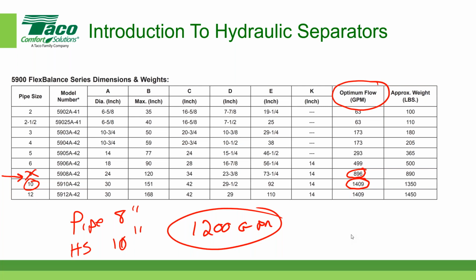But most engineers will have information in their specification that says the system has to be flushed and strainers have to be cleaned before the system is turned over to the owner or the long-term operator. The point they're trying to make is that the water or the solution, in this case water or water glycol, the most common, needs to be as clean as possible. Once you get the initial circulating and you clean out the system, you add the chemicals and all of those other maintenance related things, then what I recommend is that you blow down your air and dirt separator. You open the valve at the bottom of the air and dirt separator once a day for a few minutes to check how clean the water coming out is.